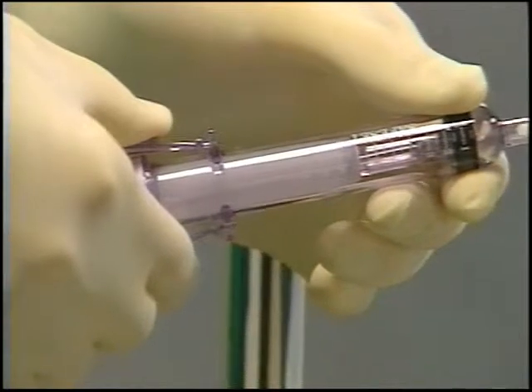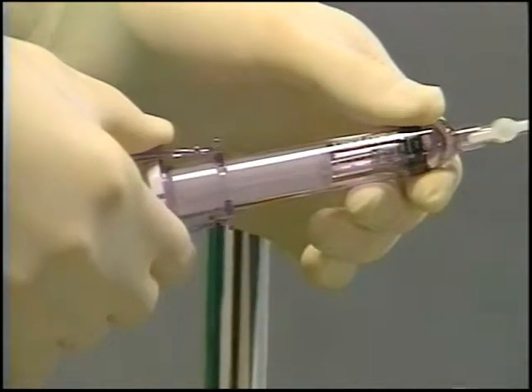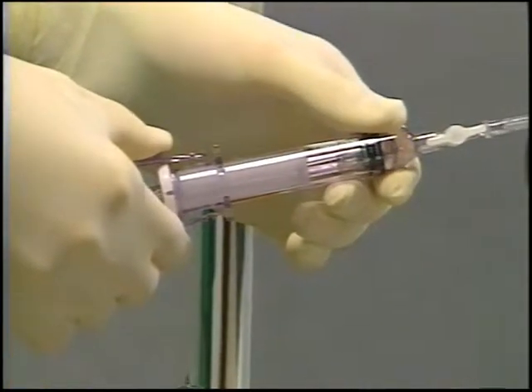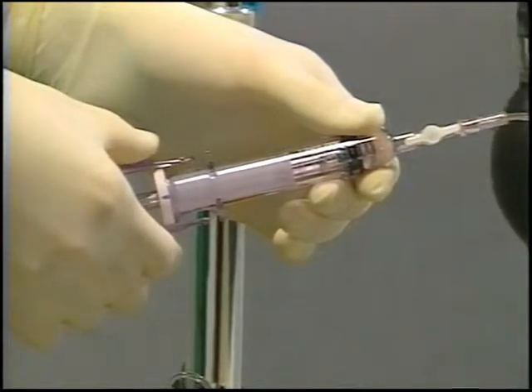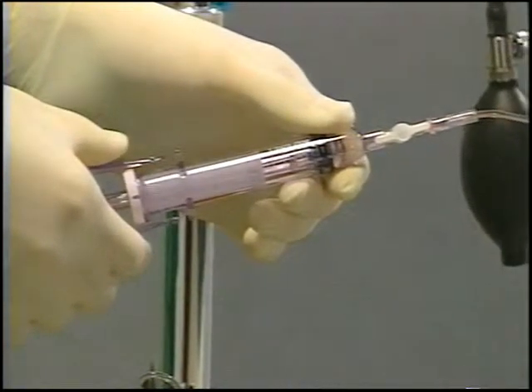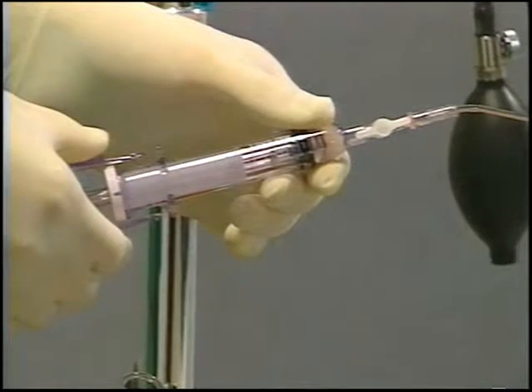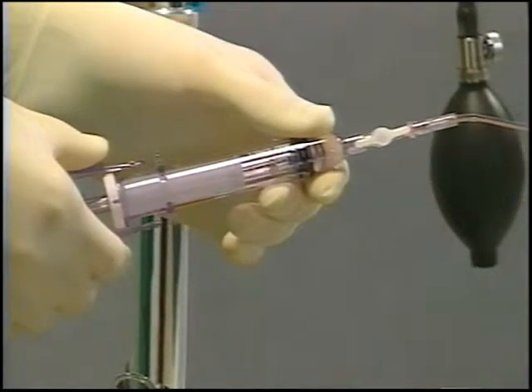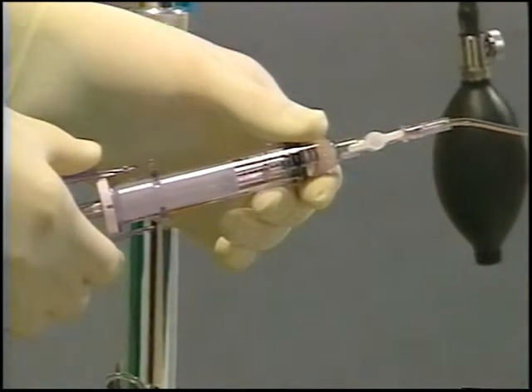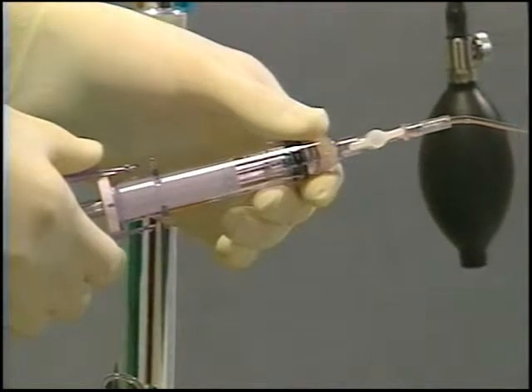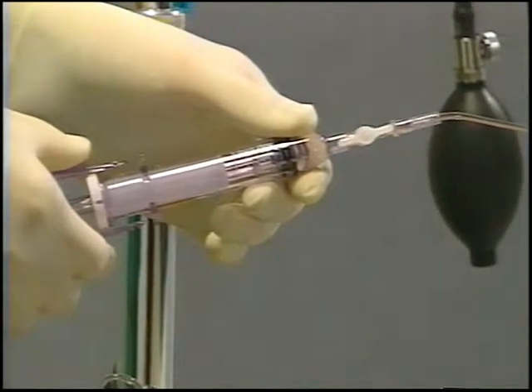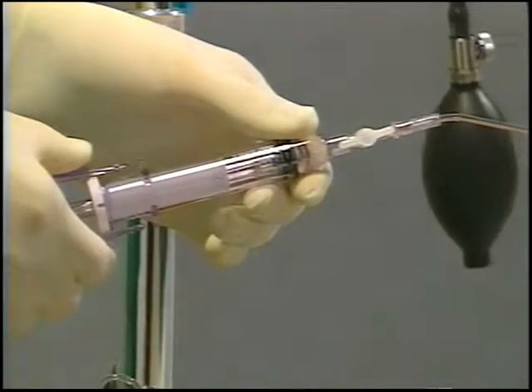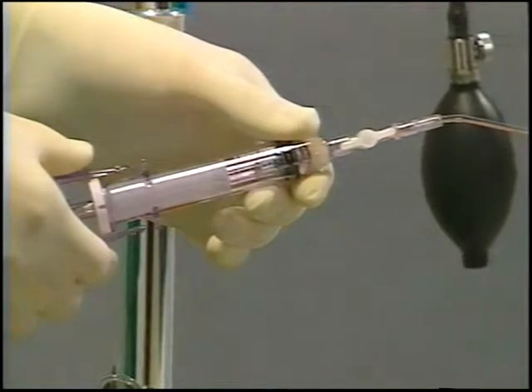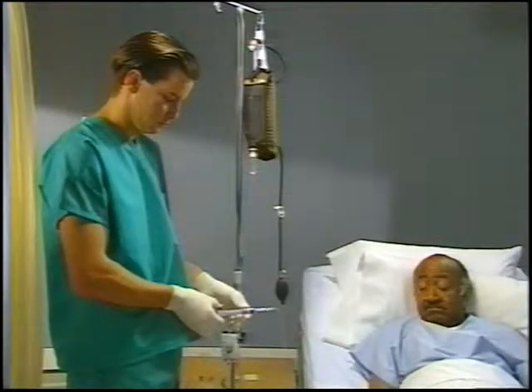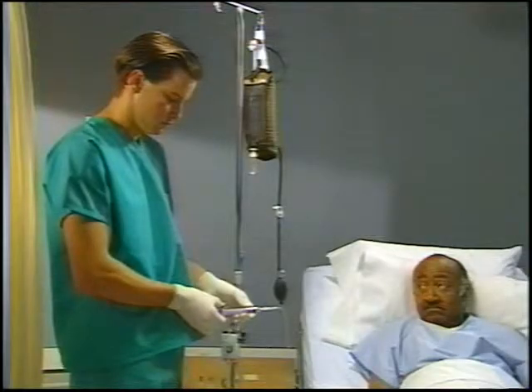Hold the reservoir and pull back on the plunger slightly to draw dead space fluid into the reservoir. Be careful to fill the reservoir no faster than 1 cc per second for normal-sized catheters, or even slower for small diameter catheters. This avoids occlusion of the catheter and also prevents blood gases from forming bubbles in the reservoir. You need to aspirate an adequate volume of blood to ensure you collect a clean sample.